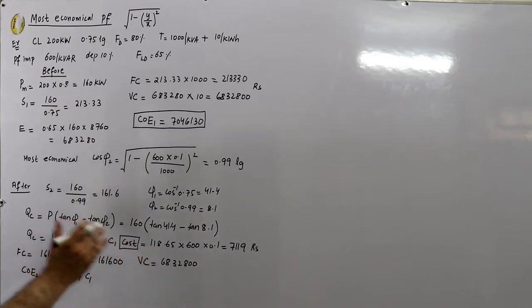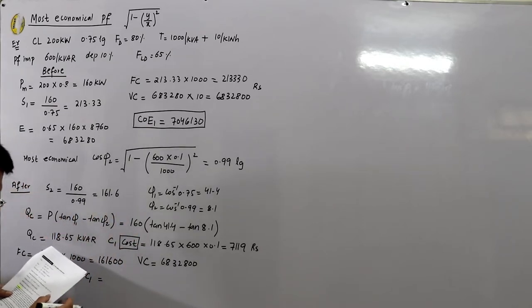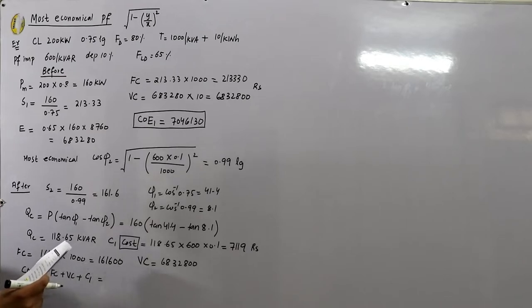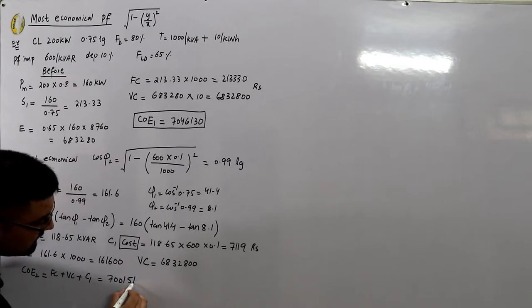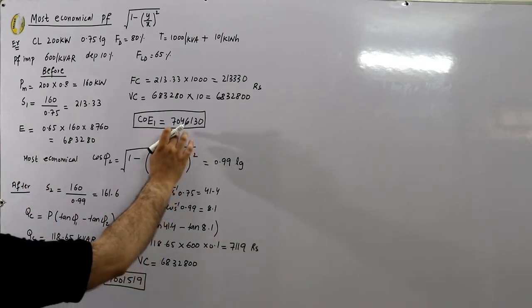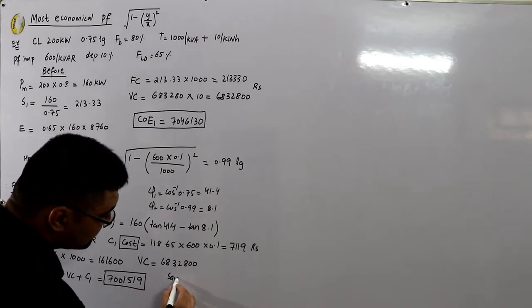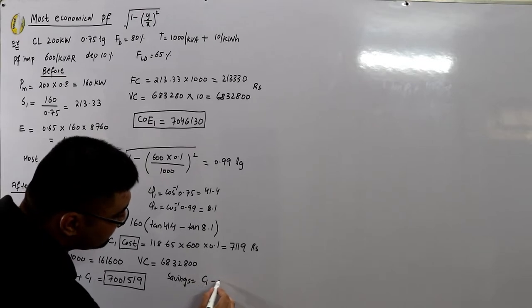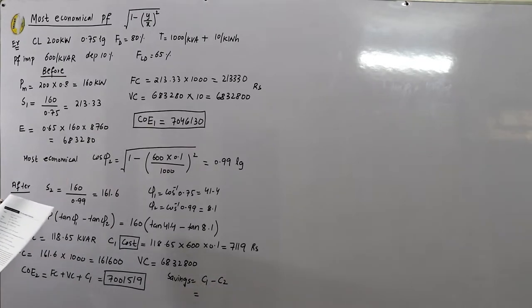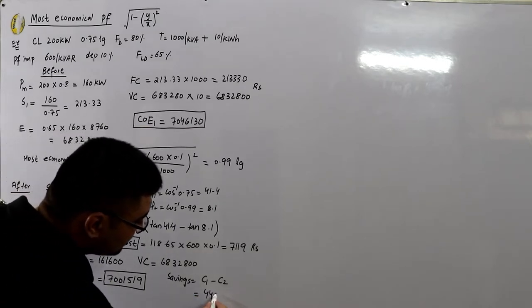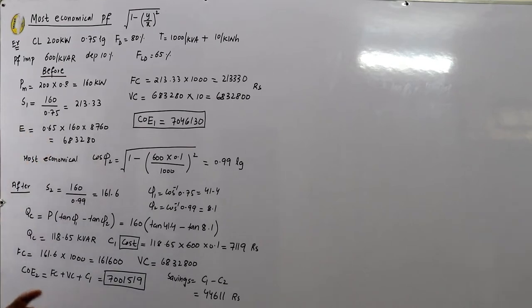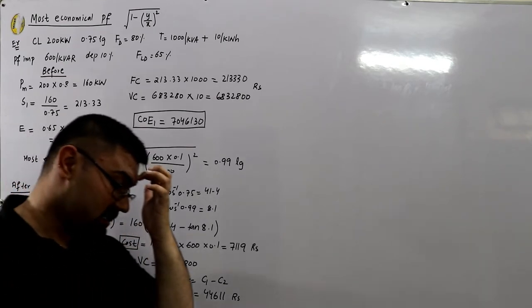The total cost of electricity after power factor correction, C₂, is the fixed cost plus the variable cost plus the cost of the power factor improvement device, which comes out to 7,001,519 rupees. Comparing with C₁, the annual savings are C₁ minus C₂, equal to 44,611 rupees saved per year by improving the power factor to the most economical value.